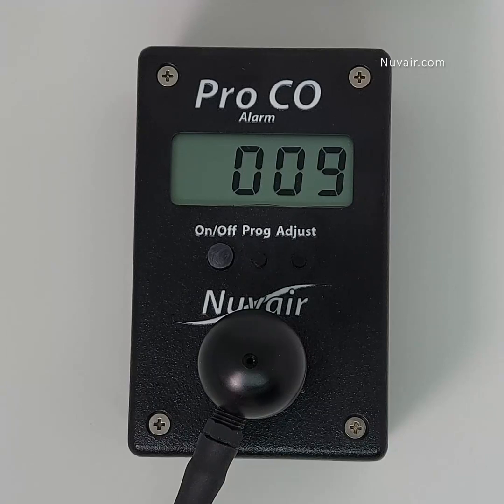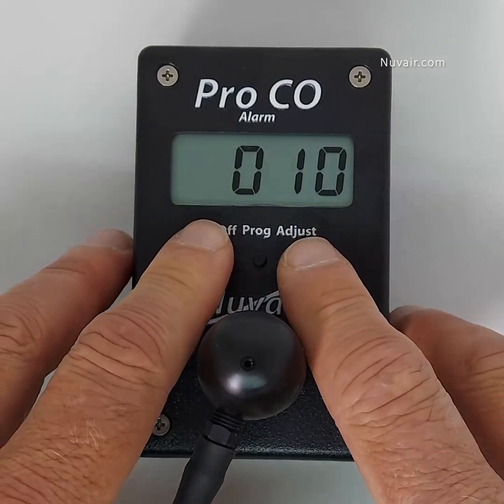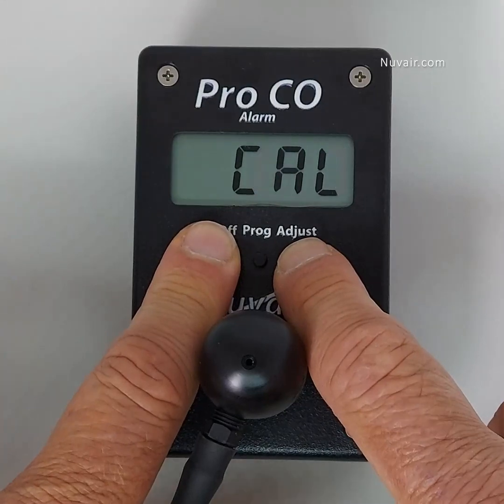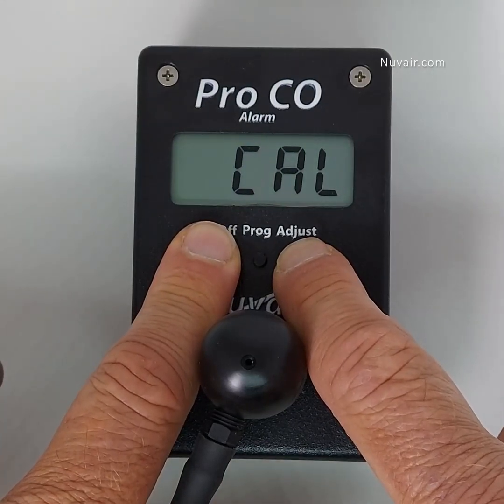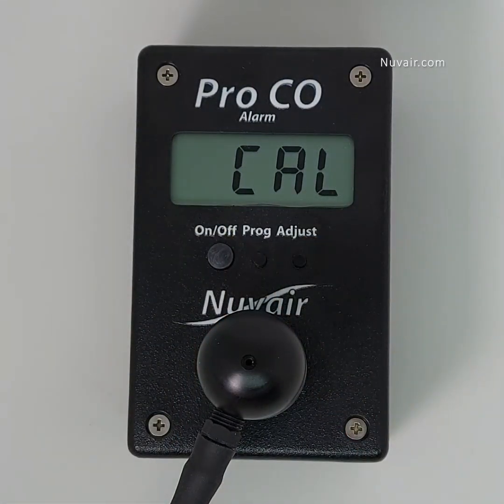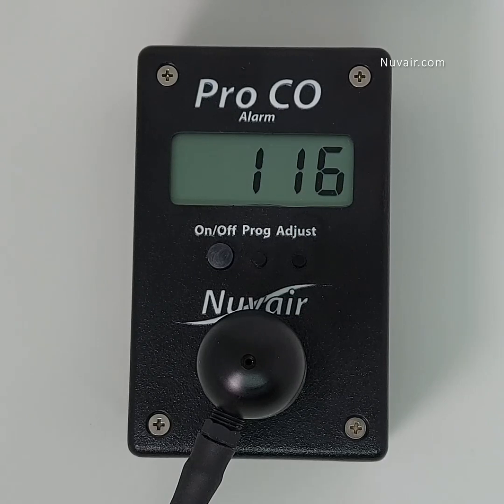Step 3. When the reading is stable, press the on-off and adjust buttons simultaneously and hold until the display flashes CAL. Step 4. The unit is calibrated once the screen returns to the gas reading display. If the reading drifts after calibration, allow the unit to sit while turned on for a few minutes, so the sensor temperature can stabilize, then repeat steps 1 through 3.